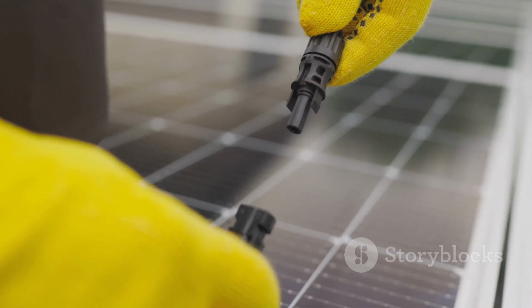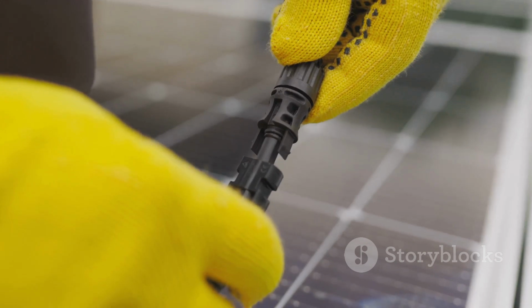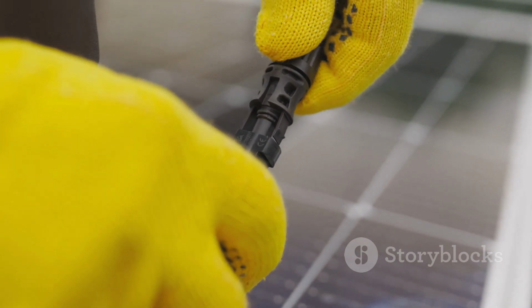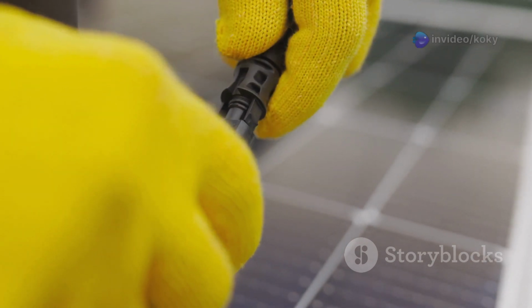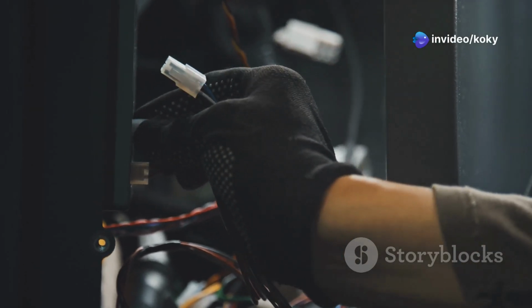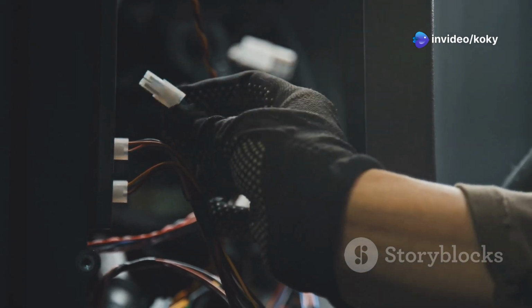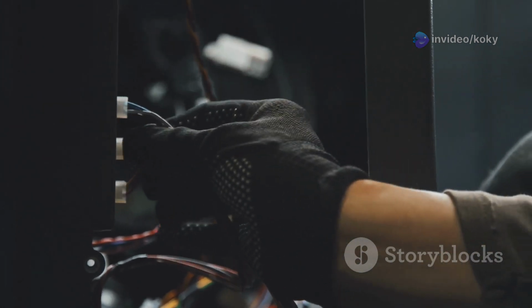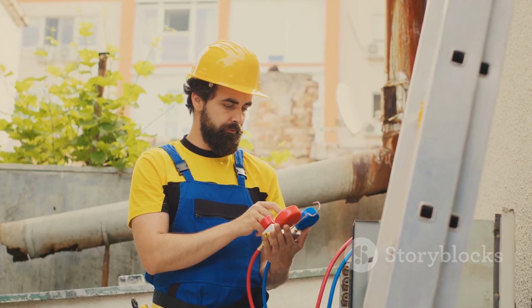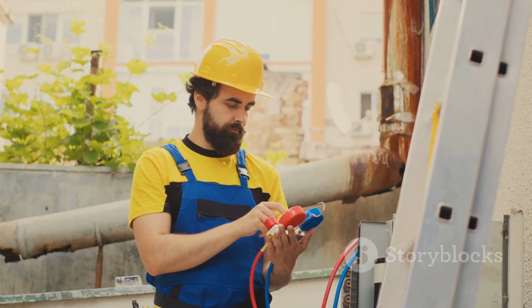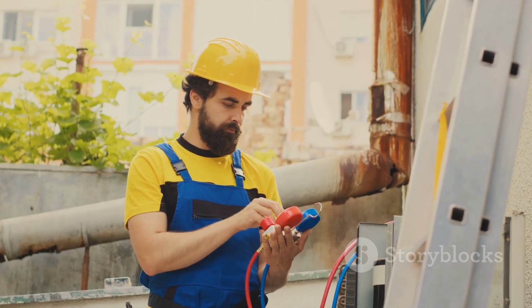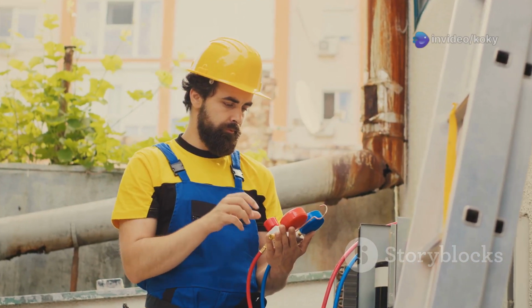Next, connect the BMS to the inverter. This allows the power from the battery to be converted into usable electricity. Connect the output of the BMS to the input of the inverter, ensuring all connections are tight and secure. Use appropriately sized wires and connectors to prevent any potential issues with power delivery and safety.